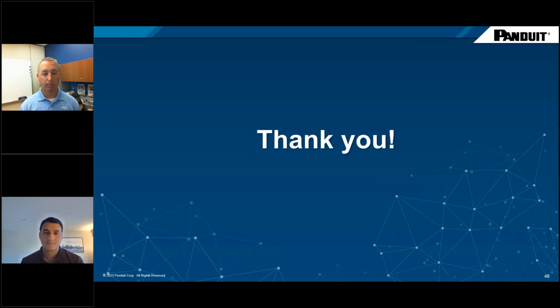Great. I have two more questions and then we'll wrap up. Can Class 4 and PoE be located in the same wiring bundle? That's a great question, and I'll tell you frankly that there is some confusion around this right now. So the short answer is yes, they can be. There just are some requirements today, such as putting up a barrier or allowing for, I believe, a 2-inch separation. But we have to realize that these requirements in the standard today came out almost over a year ago, before systems were out, and so there's been a lot of learnings between vendors and UL, and I can see the ramifications coming into these standards to make that requirement a little bit more lenient.